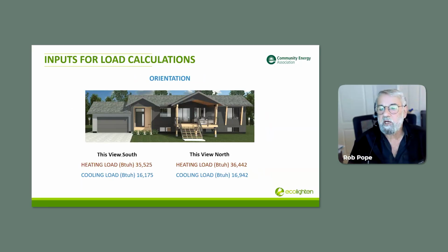And now, imagine if there were no overhangs here in the south view. Now this south view would have had a cooling load substantially higher. And we'll see that later. It wouldn't be 16, it would be higher. And then we turn it around and suddenly it goes down. What would happen if we got the orientation wrong in that situation is we'll have an undersized cooling capacity for the house in our load calculations.